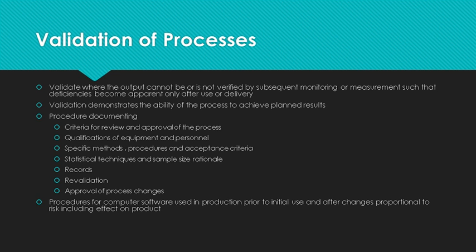If software is used to control production, the software must be validated prior to using the software and, as appropriate, after changes. Check with your registrar as to how they view software validation. Many but not all organizations view commercially available software as validated by the software company. Some may require all software to be validated. Others will require your organization to obtain copies of the software validation from the software companies. And others will accept that if you haven't modified the software, it was validated before sale.